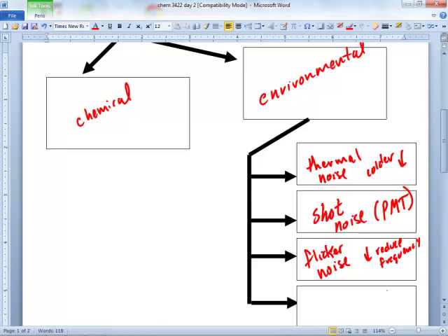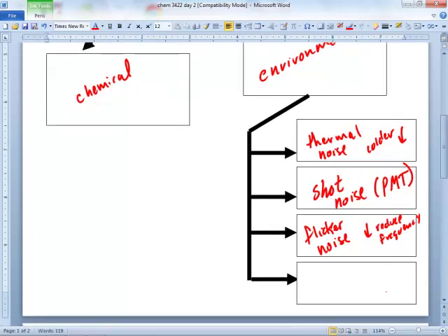But that's why in some instruments, if you really dig into their guts, like I had to once on our UV-vis that broke down, there's something they call a chopper. If you put a little piece of paper in where the cuvette goes, you see the light, but that light is actually, if you could have a fast eye, flickering. Well, all they have is a spinning disc with little holes in it, spinning in front of the light source. So the light's really going across at a certain frequency. That's what they're messing with. They're trying to reduce flicker noise and get it into a nice frequency range. It's one of the things that they're trying to work with.